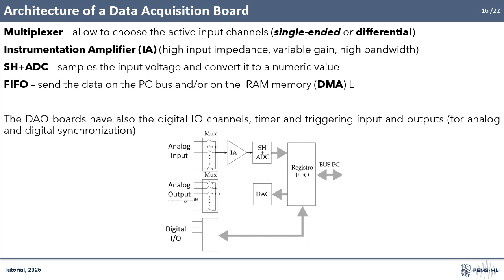This kind of connection saves one input terminal and can double the number of signals connected, equal to the total number of pins, but on the other side, it suffers from a higher noise level and no rejection of the common mode noise. It is useful when no particular requirements of noise rejection are asked, or there are no strict accuracy specifications, for example, the temperature measurement for the control of the temperature in a house.